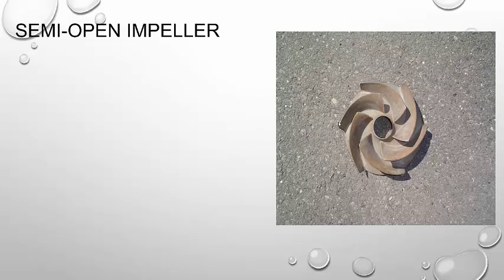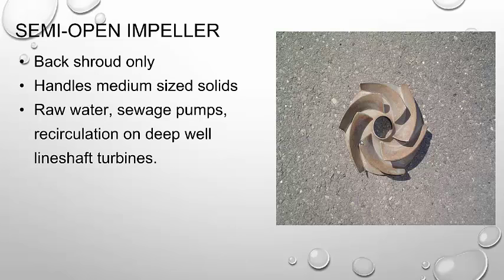Semi-open. We can handle still a fair amount of solids through this. I'm not going to have as high efficiency as I get with a fully enclosed impeller. But I can get better efficiency than I can with an open impeller. And I have the back shroud complete. If I stick a shroud on top, I've got the closed impeller. High efficiency, low tolerances for solids, and low tolerance for spacing between the impeller and the volute. But because of that, I'm very, very efficient.